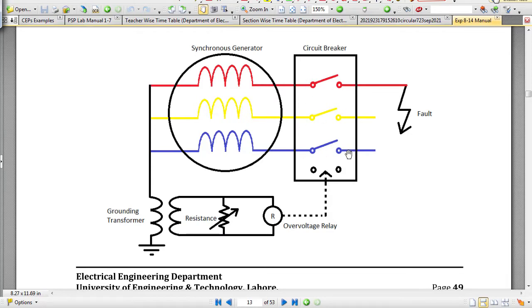So we can provide a very effective and yet very sensitive protection by inserting an over voltage relay across this resistance, which will respond to the voltage which will appear in case of a line to ground fault.